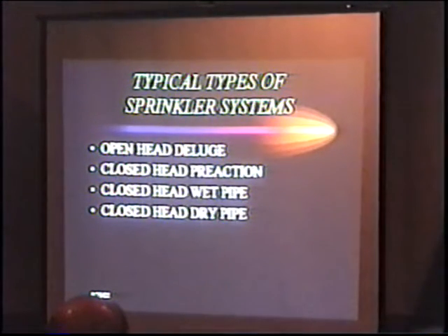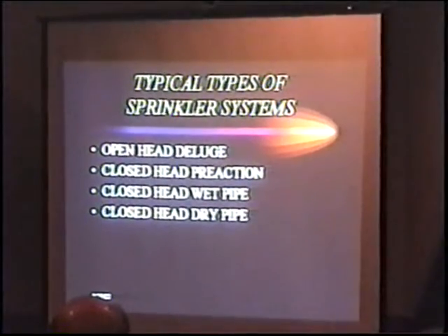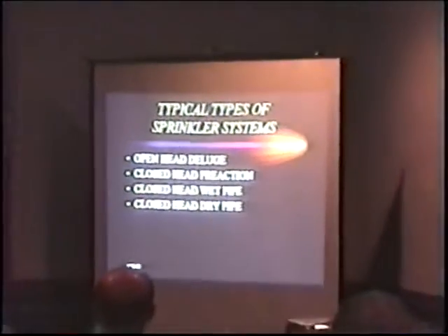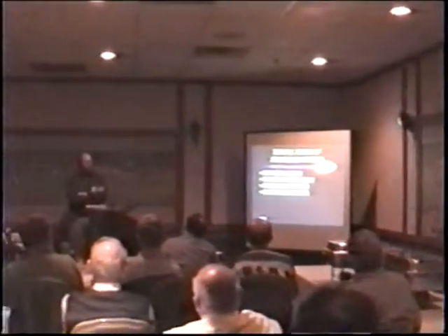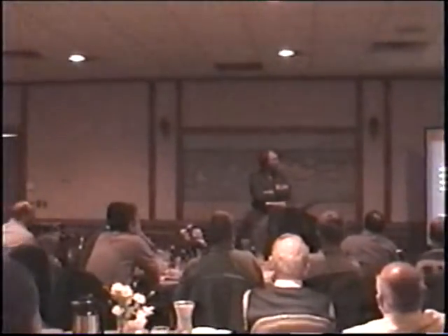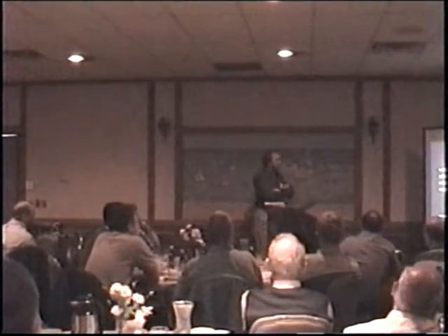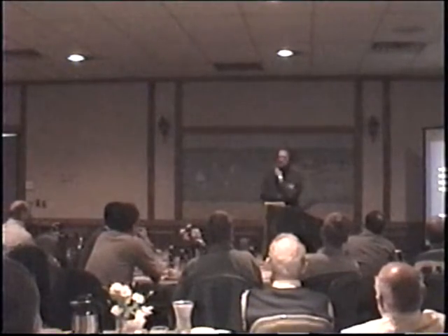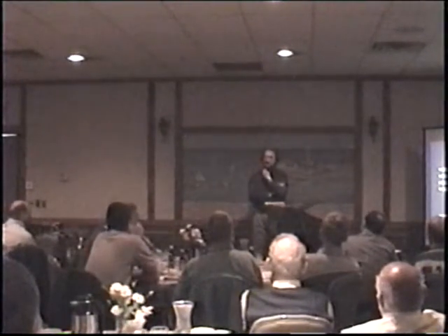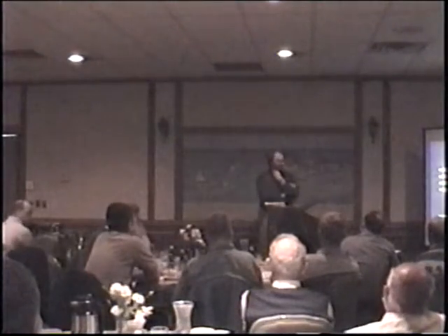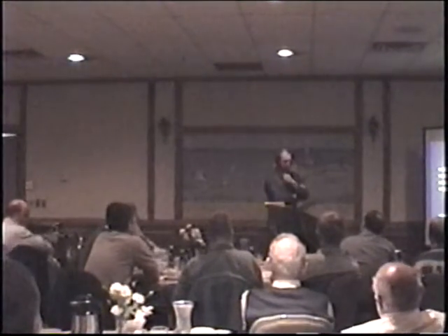Closed head wet pipe systems are also becoming more and more common, with the advent of large storage facilities, drum warehouses, processing areas, so we're seeing more wet pipe systems used. Closed head dry pipe, you can use foam in these, you just don't see a lot of dry pipe systems because they're kind of a slow reacting sprinkler system. And you have flammable liquids, so you don't want slow reacting sprinkler systems. The top three are the most common you're going to find.